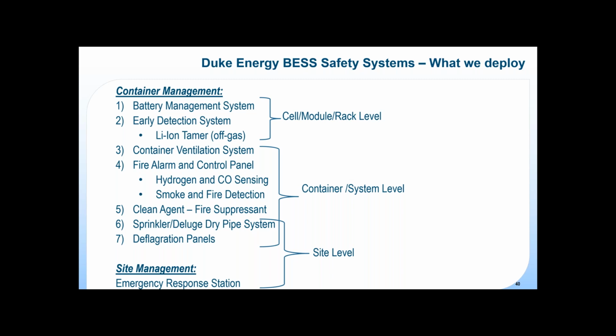Then we move on to a container ventilation system. All of our containers can have an exhaust system that allows us to bring fresh air in and exhaust any gas buildup inside the container. That's automated, controlled by the hydrogen and CO sensing systems when it needs to take effect, or we can manually control it from the emergency response station that I'll address in a minute.